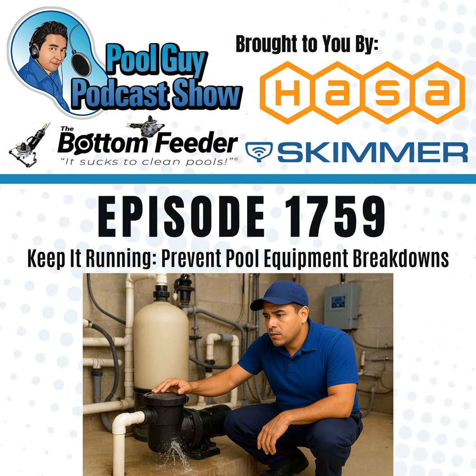The Pentair air bleeder assembly that's on top of their FNS Plus and Clean and Clear Plus filters is extremely fragile. So when you're taking that off to clean it, try not to drop the lid, because you try not to break that also when you're opening it and closing it. I've broken those before. So carry an extra one of those on your truck as well, because chances of you breaking one of those is very great, because I've broken them myself.